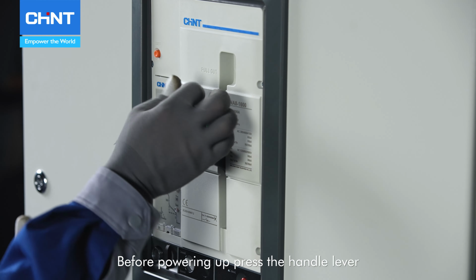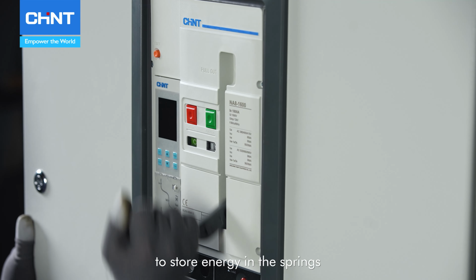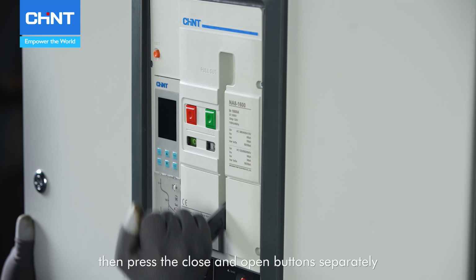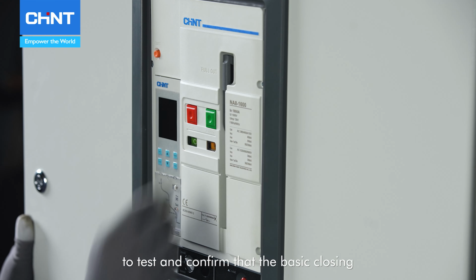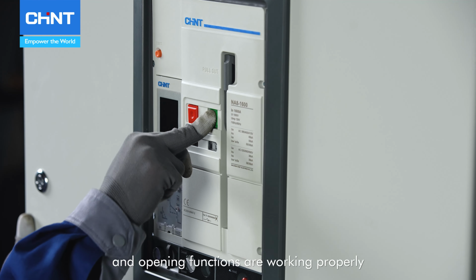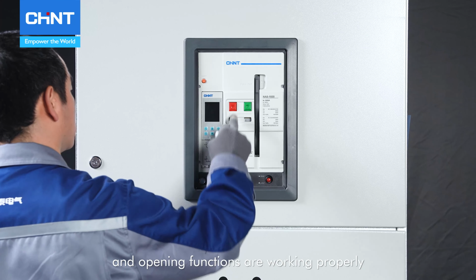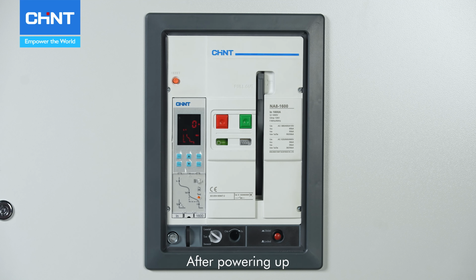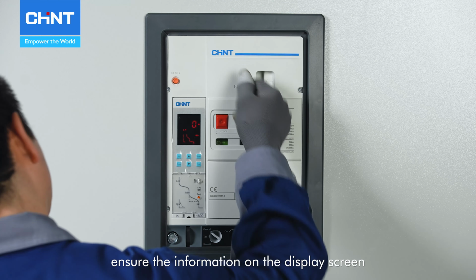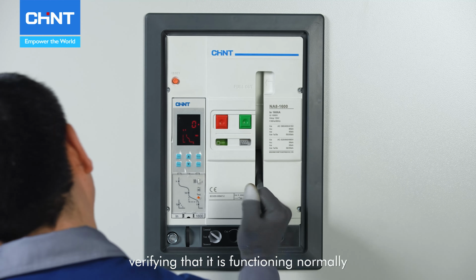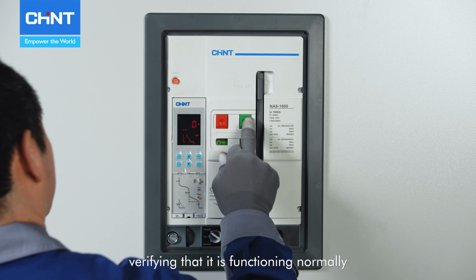Before powering up, press the handle lever to store energy in the springs, then press the close and open buttons separately to test and confirm that the basic closing and opening functions are working properly. After powering up, ensure the information on the display screen is correctly shown, verifying that it is functioning normally.